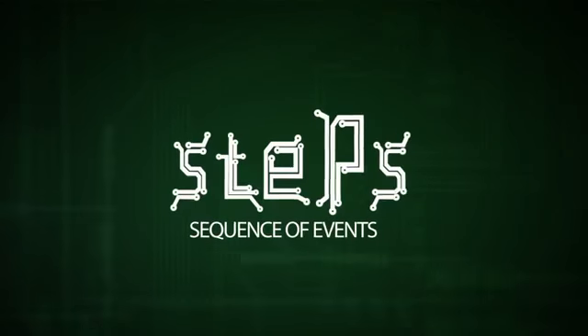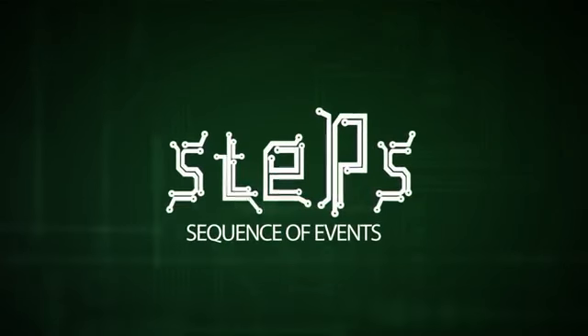I typically like to program a step for each action. So if something is going to happen, that's going to be a step. So if something is going to extend, that would be a step. If something is going to retract, that would be a step. So what I'd like to do now is let's look at the station and let's really figure out how many steps we're going to need for this particular station.